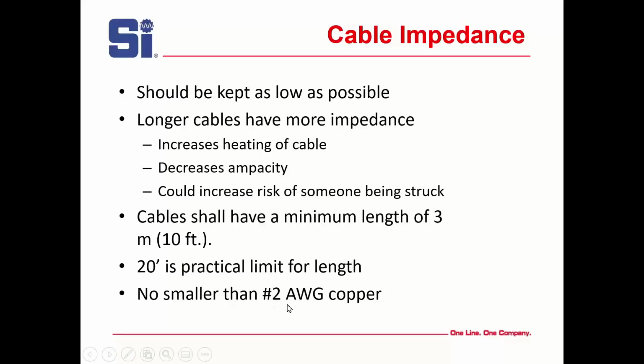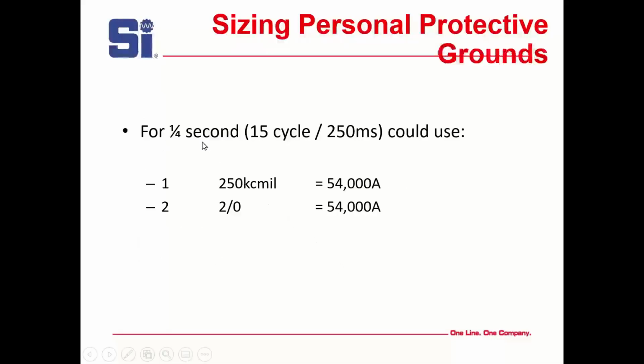OSHA says no smaller than number 2 AWG copper, not aluminum. AWG copper. That's the law. So for a quarter second, looking at 15 cycles, 250 milliseconds, which by the way is a quarter second, you can use one 250 kcmil, comes out to 54 thou, or you can use two 2/0, and that comes out to 54 thou. And the chances of you hitting exactly the short circuit current are pretty slim. Usually it's quite a bit less, but make it as close as you can.